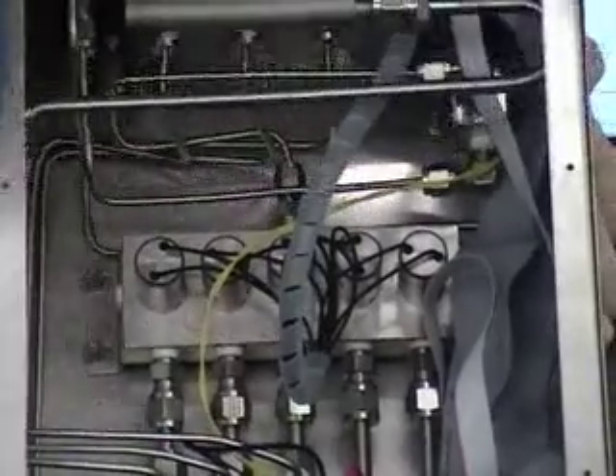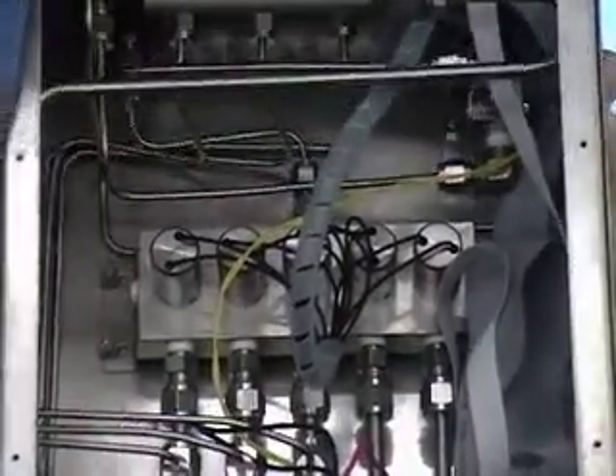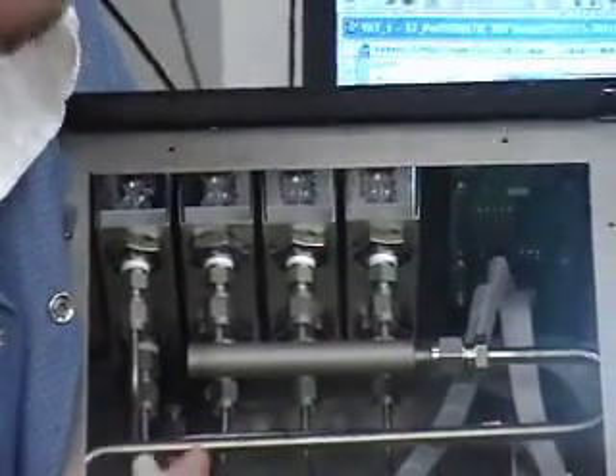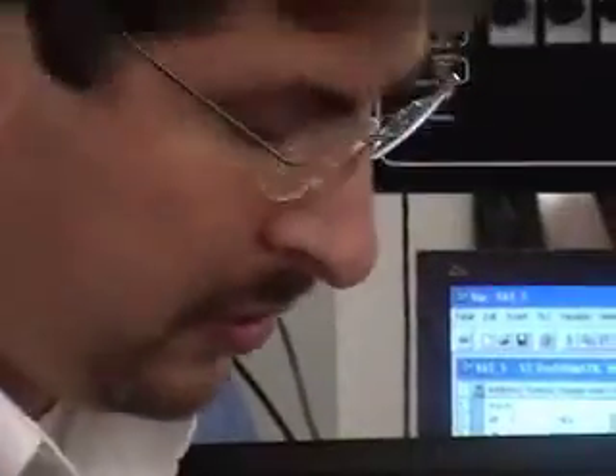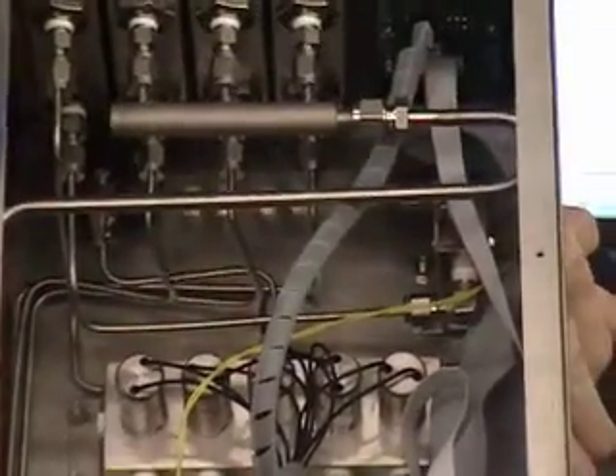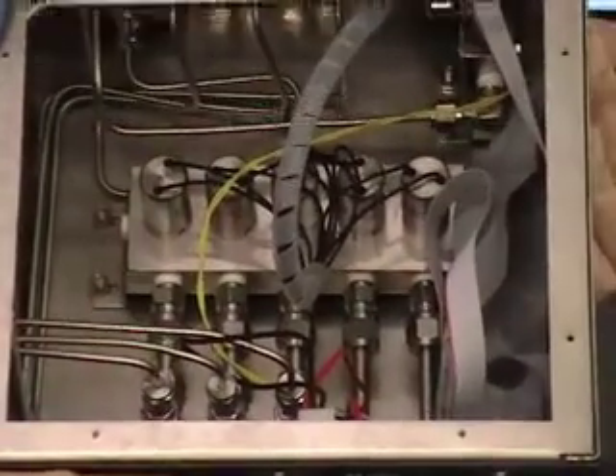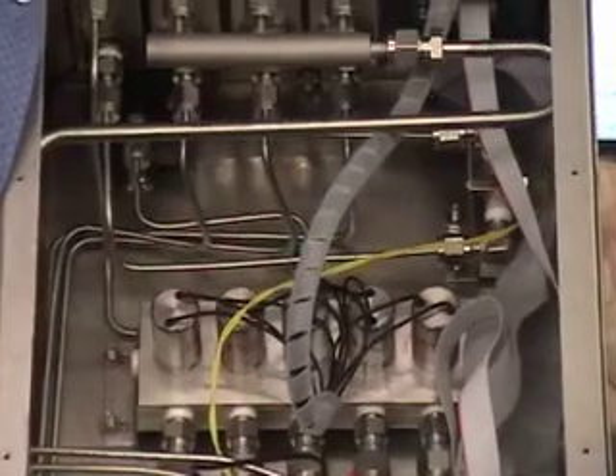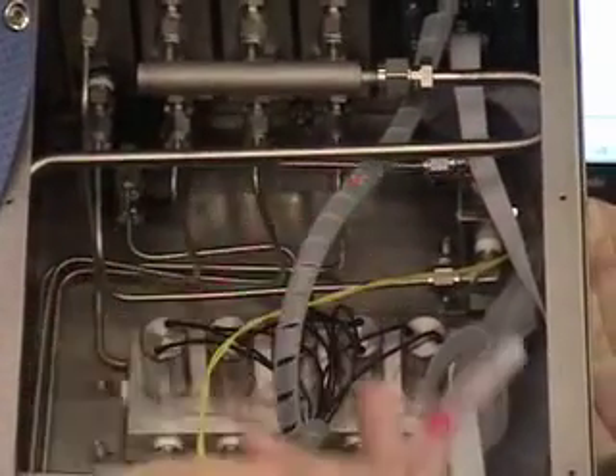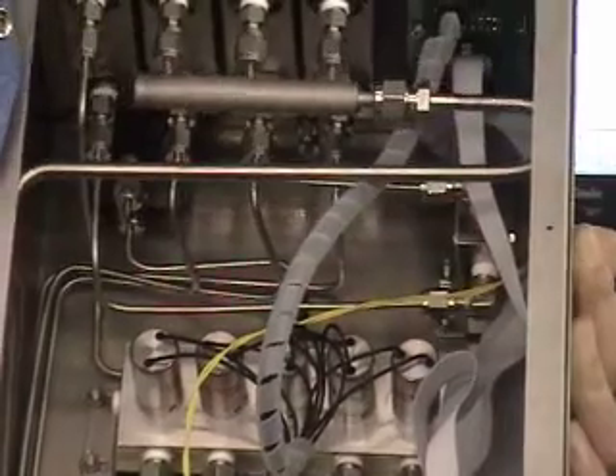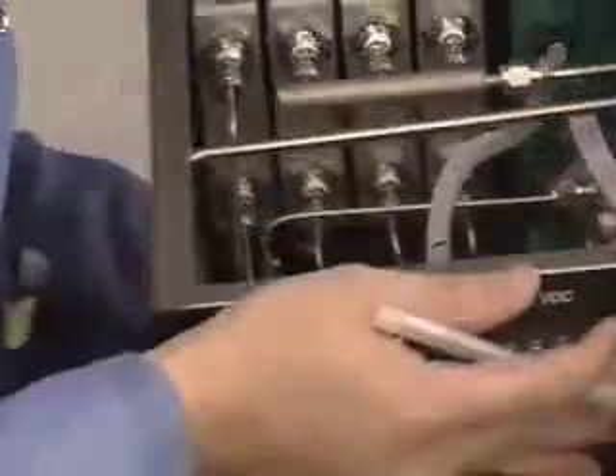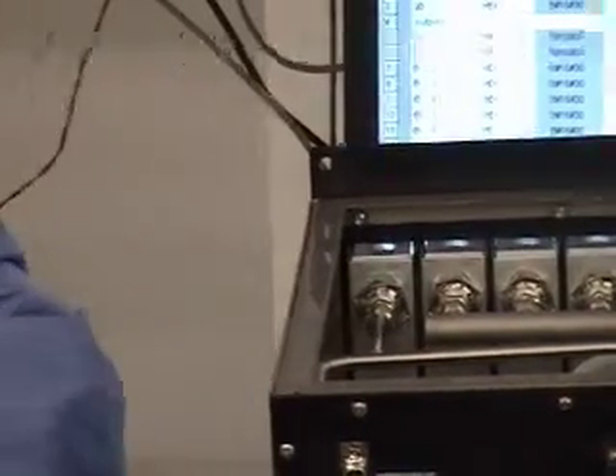We can see that we've got 5 valves here. 3 are for the samples, 1 for the zero, and 1 for the span. They are all controlled by the network, the Profibus network, which sends commands so that we can select which valve will open and which ones will be closed. Or we can do a manual override, where we control the valves through the front, or we can have the analyzer send commands through the RS-232 to select the span gas, the zero gas, or one of the sample gases. As well, we can have a computer override. The computer override can have digital inputs or relay closures on this connector over here.